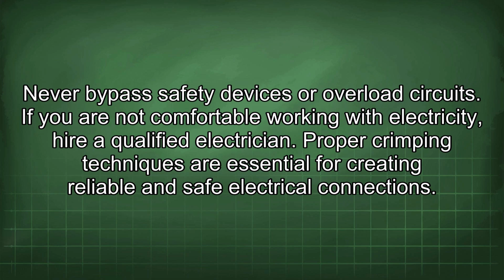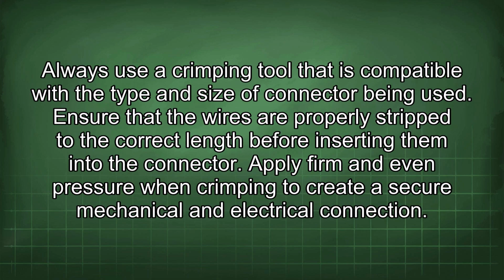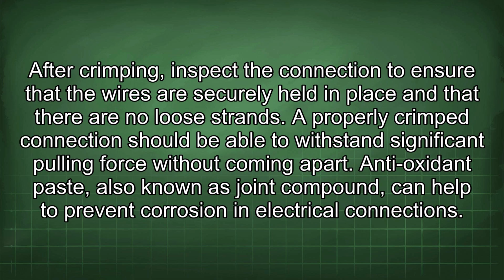Proper crimping techniques are essential for creating reliable and safe electrical connections. Always use a crimping tool that is compatible with the type and size of connector being used. Ensure that the wires are properly stripped to the correct length before inserting them into the connector. Apply firm and even pressure when crimping to create a secure mechanical and electrical connection. After crimping, inspect the connection to ensure that the wires are securely held in place and that there are no loose strands. A properly crimped connection should be able to withstand significant pulling force without coming apart.